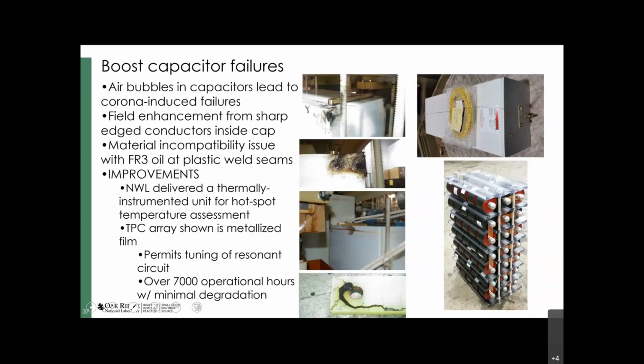We did have one company, and they're out of Florida, and they've got a pretty good solution for us. The problem with it, though, is an oil compatibility and/or maybe even poor thermal welding of the plastic problem. So we don't exhibit any kind of arcing per se, but eventually the case starts to crack. And so right now, what we're doing is replacing those about every 3 years, just as preventative maintenance.